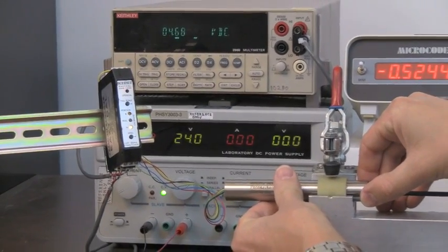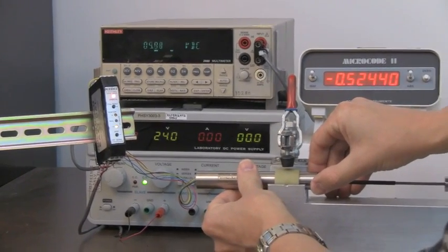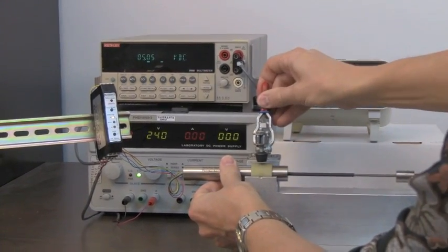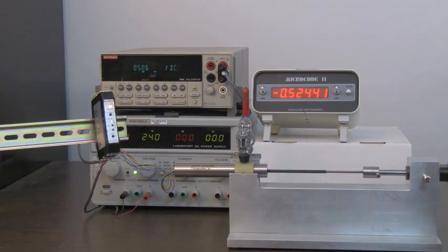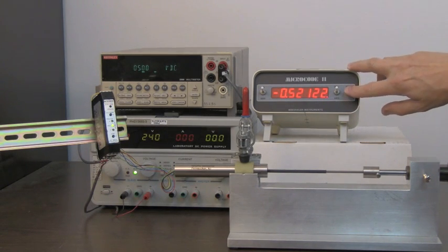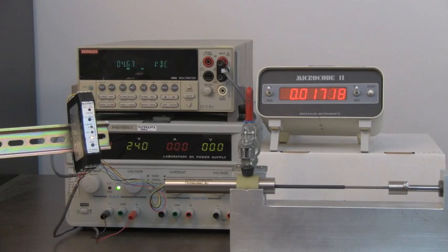We then position the coil in the test fixture as closely as possible to null and lock the coil in place. Next, we adjust the digital micrometer head until the null LED indicator lamp is steadily illuminated. Being at null, we now reset the digital micrometer readout to 0. Next, we'll displace the LVDT core by negative 0.5 inches using the digital micrometer head and readout. This will take us to the negative end or 0-inch position of the LVDT stroke range. In relation to the EAZY-CAL, this will be the 0-volt DC output position.